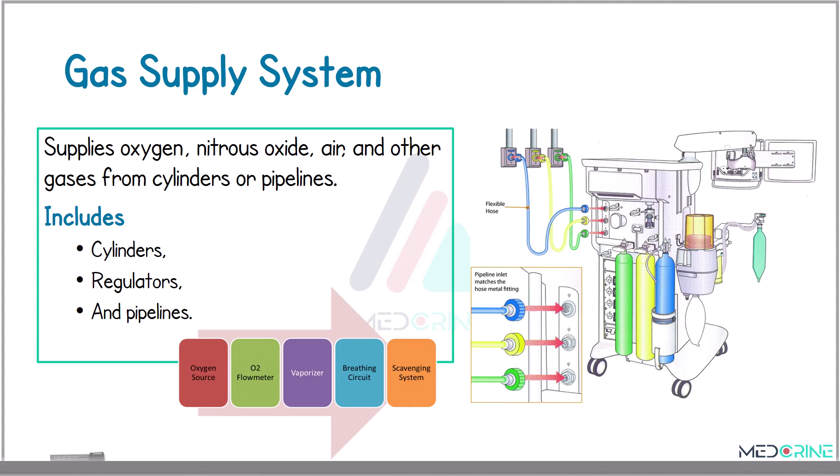The gas supply system delivers oxygen, nitrous oxide, air, and other medical gases from either high-pressure cylinders or hospital pipelines. It comprises a cylinder, cylinder regulators, and connecting pipelines, which ensure a continuous and safe gas supply.